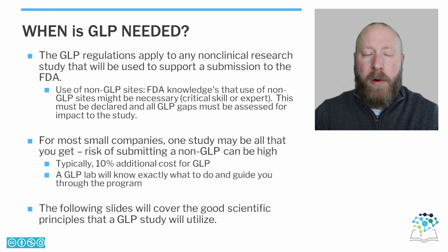Now, for most programs, one study is all you're going to be able to do, mainly due to the cost of the studies themselves. So the use of a non-GLP study for your submission may be pretty high risk. If the FDA feels that that study does not have the necessary data integrity or show the necessary safety results, you may be required to redo your work. Now, typically, the cost of doing a study GLP versus non-GLP adds about 10% over the original cost. In my opinion, this cost is minimal compared to the risk of submission of a non-GLP study.